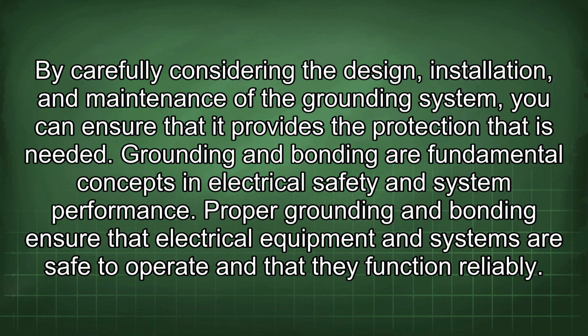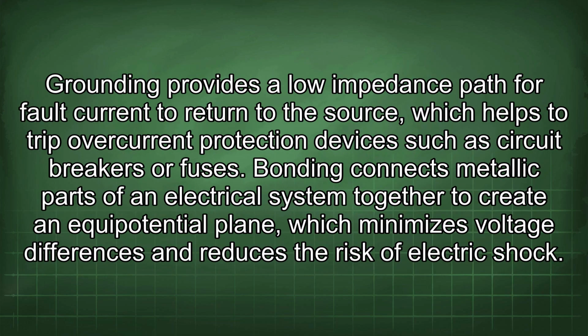that is needed. Grounding and bonding are fundamental concepts in electrical safety and system performance. Proper grounding and bonding ensure that electrical equipment and systems are safe to operate and that they function reliably. Grounding provides a low impedance path for fault current to return to the source, which helps to trip overcurrent protection devices such as circuit breakers or fuses. Bonding connects metallic parts of an electrical system together to create an equipotential plane, which minimizes voltage differences and reduces the risk of electric shock.